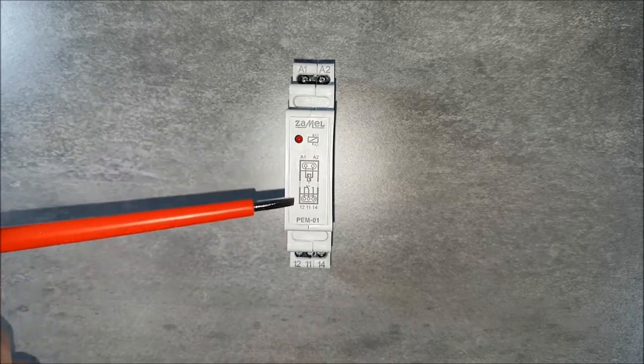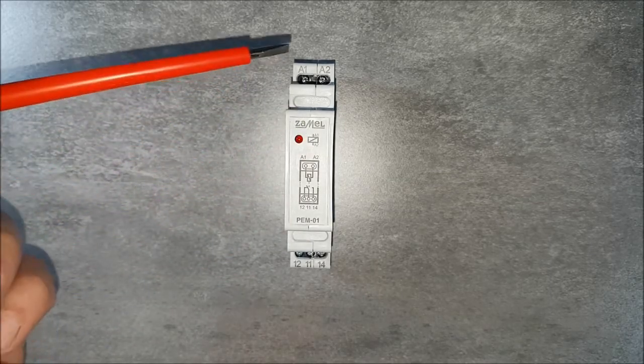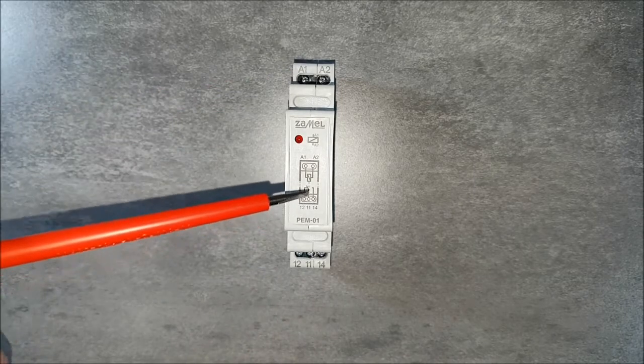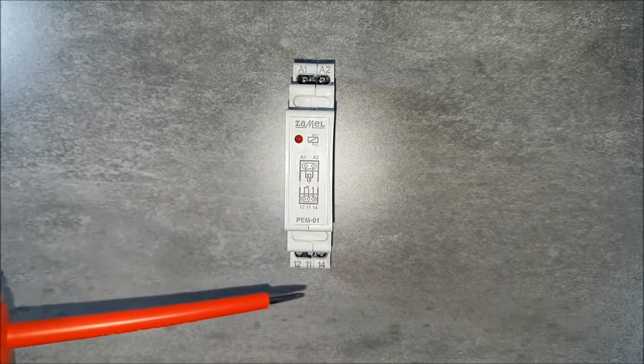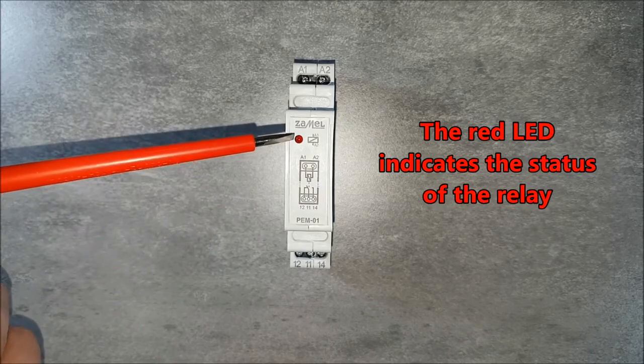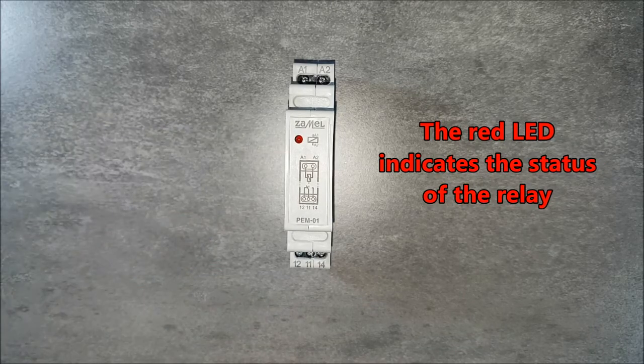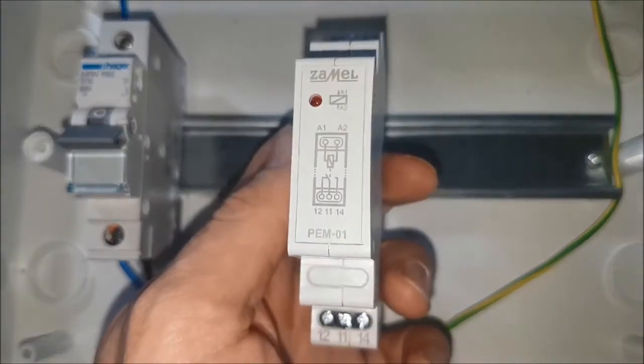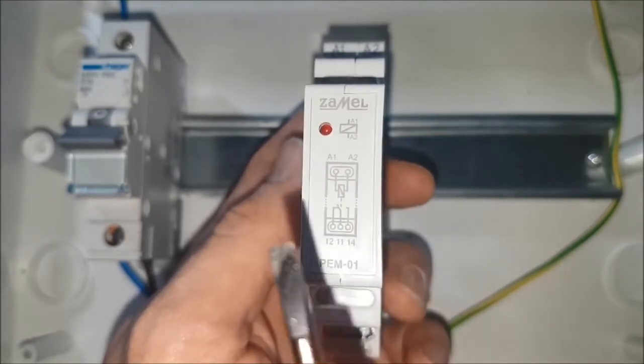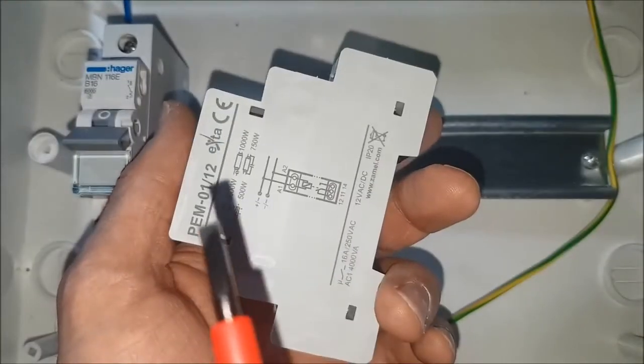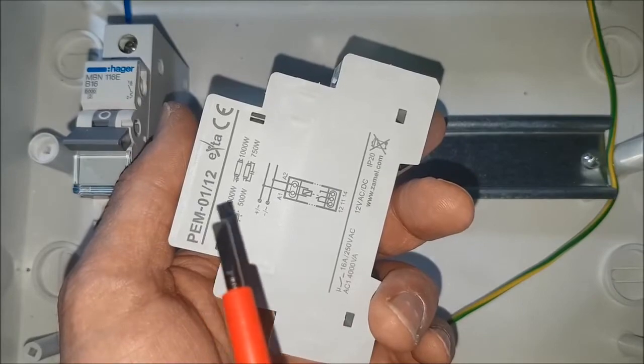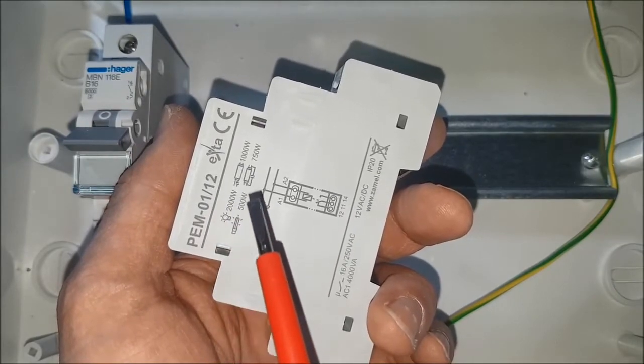Internal diagram of the device is on the front panel. This facilitates assembly task. Coil of the electromagnetic relay, as well as the output relay contacts are shown. The front panel has a red LED to indicate the status of the relay. Put the PEM-01/12 relay on the TH35 rail. Device connection is facilitated by the side diagram and the table of acceptable loads.